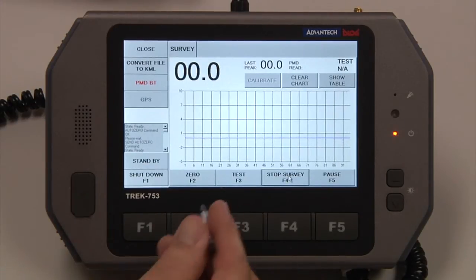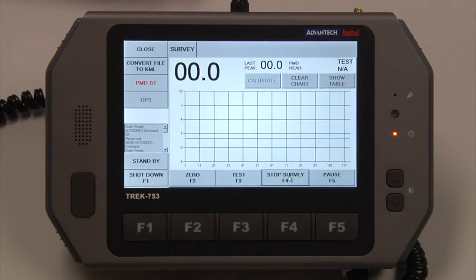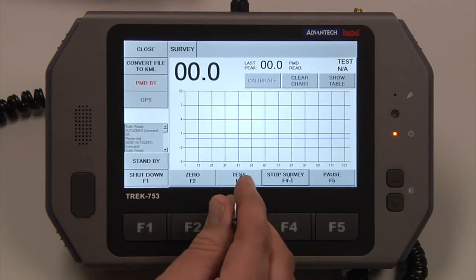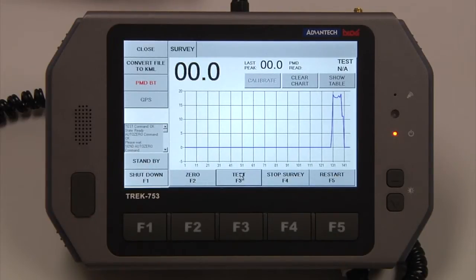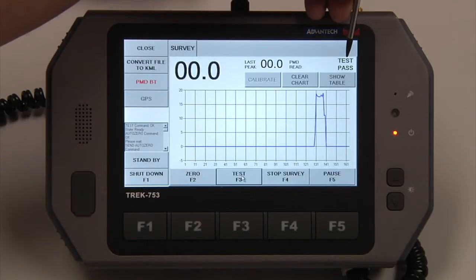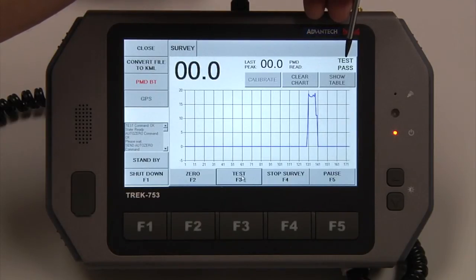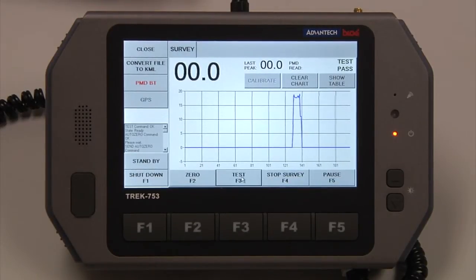At any point, if you want to test the PMD, there's an internal test cell built into the receiver. If we just hit the Test button, it will drop that internal cell in and then eject it. Up here in the upper right, it will either show Test Pass or Test Fail. If the test were to fail, we would want to try to run a calibration.